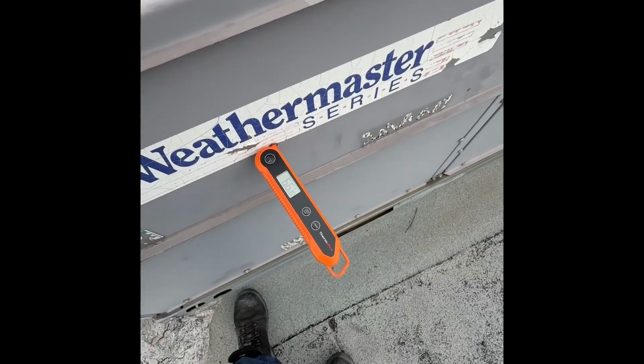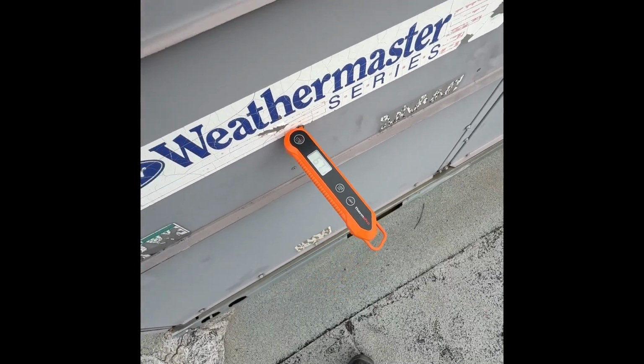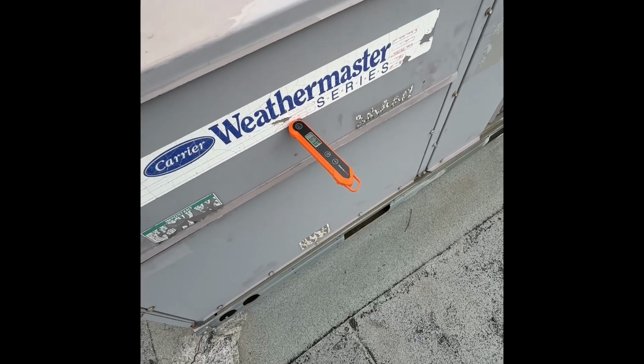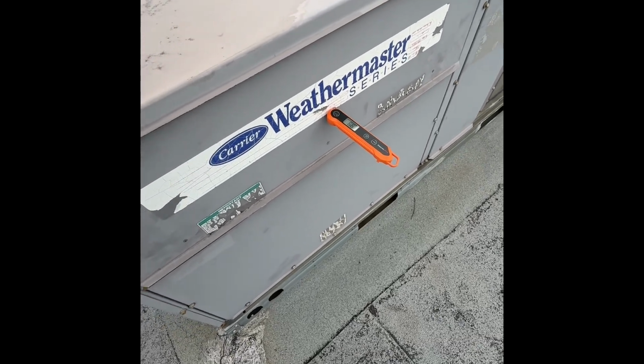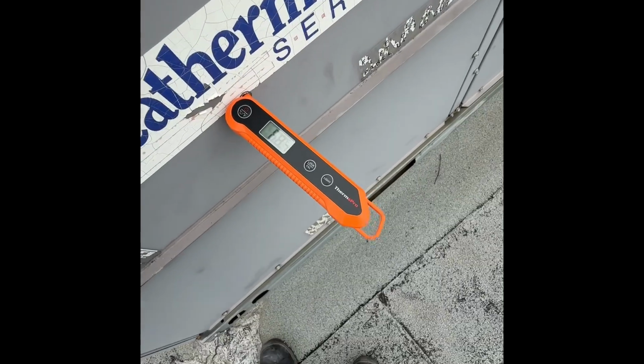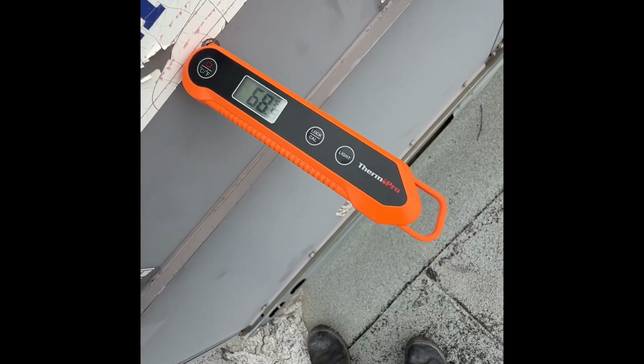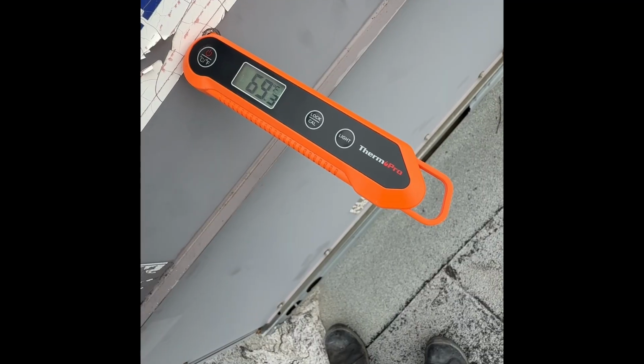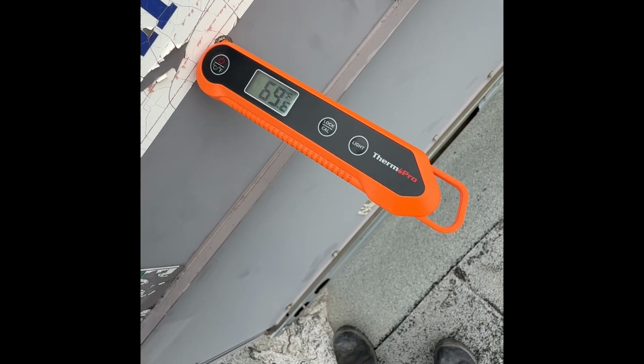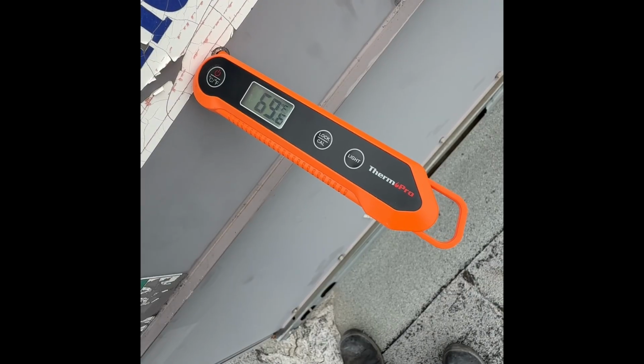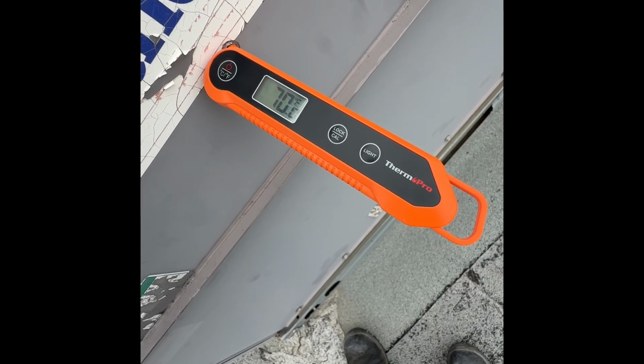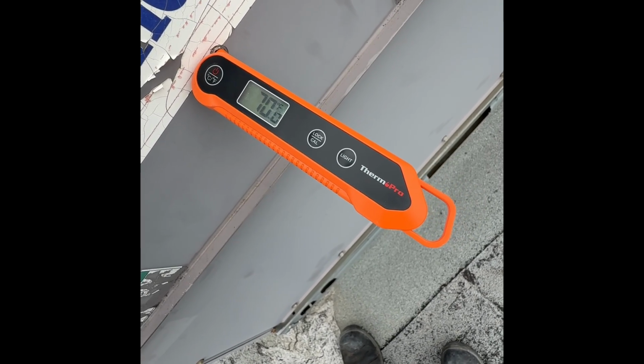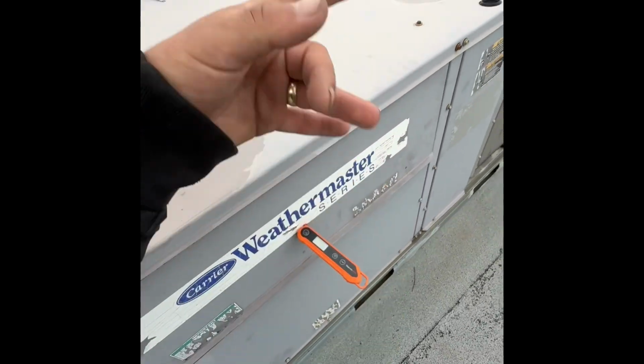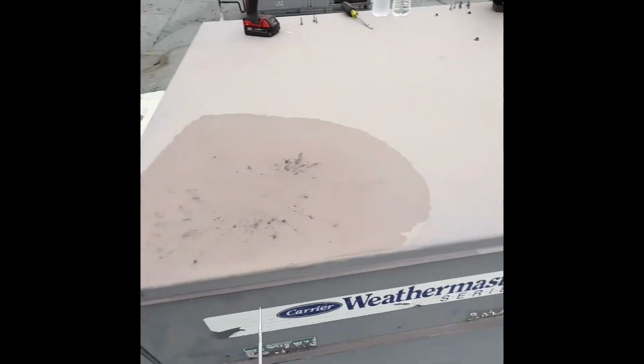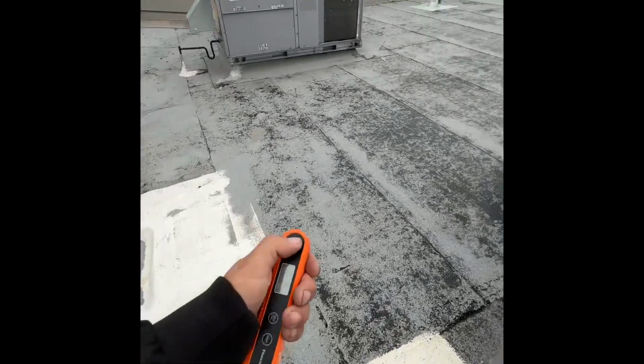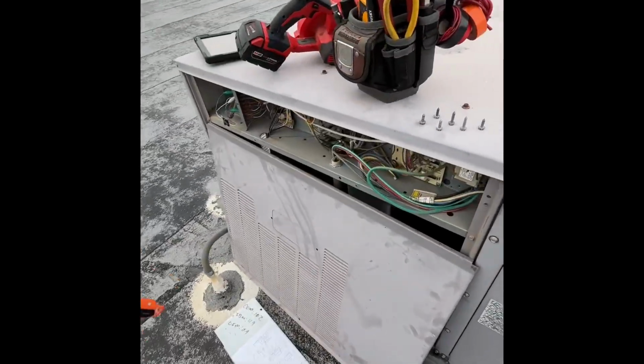So we got 54 degrees. So to get a perfect split in a perfect world for right now, we want plus 15 degrees of that, or 10 to 15 degrees of that. And we got 68 and climbing, it looks like, so that's good. 74 would be about a 20 degree split. So we're at the 15 mark right about there. So there you go. You can take photos of that, update it to your company Service Titan portal app for your inspection forms, whatever you need to do. Take all the photos and you're done there.